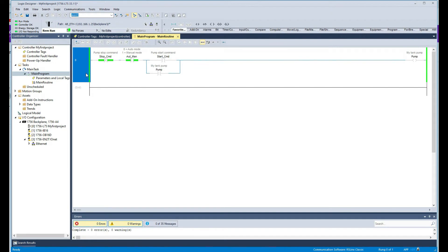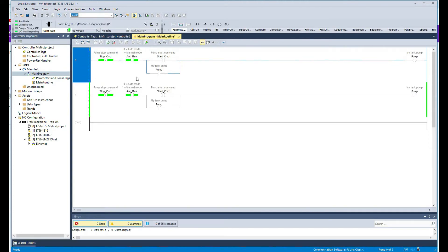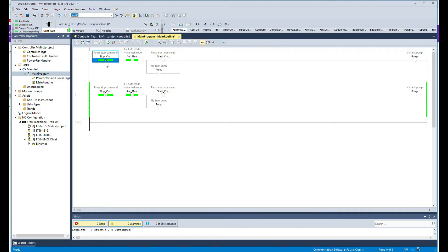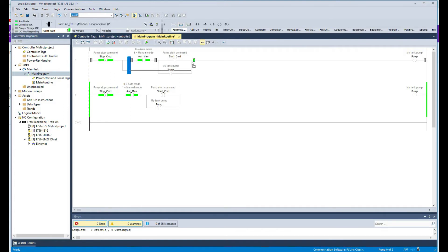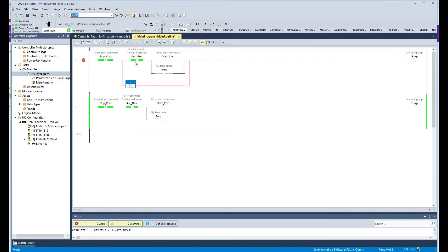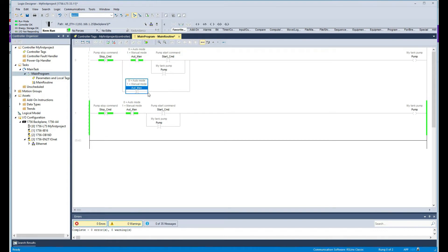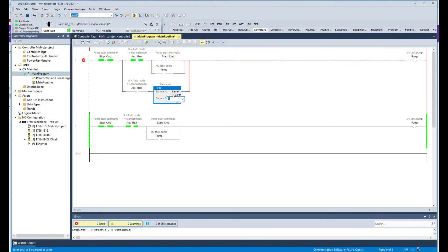There are some limitations to what we can do online versus offline. As I mentioned, in manual mode we control with push buttons, in auto mode we control using the level. Notice the stop button is upstream of the mode selection because I want to stop the pump regardless of which mode we're in. I'm going to add in parallel the auto mode branch — when the auto/manual tag is at zero, we are in auto mode. Then I'll add a compare instruction.